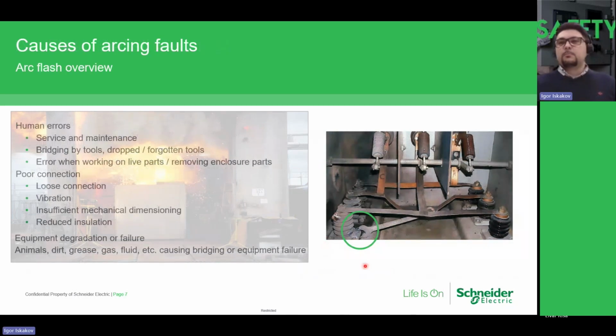So if we speak about what this brings to arc flash, 80% of arc flashes are human error. People make mistakes, people are not perfect. It's always service and maintenance: bringing tools, dropping tools, falling tools, forgetting tools in the switchgear. Errors with working parts, removing enclosure parts during operation and putting the enclosure back in the switchgear. Also some misalignments and others can be the cause of the arc flash.